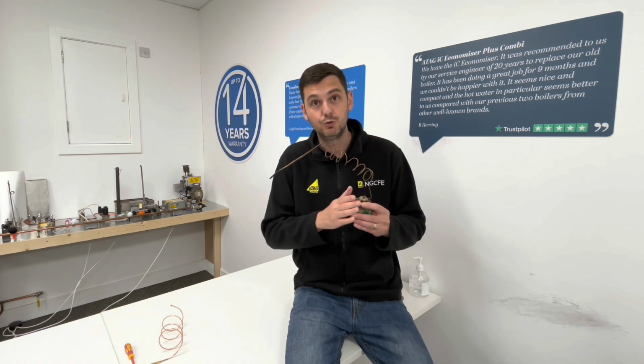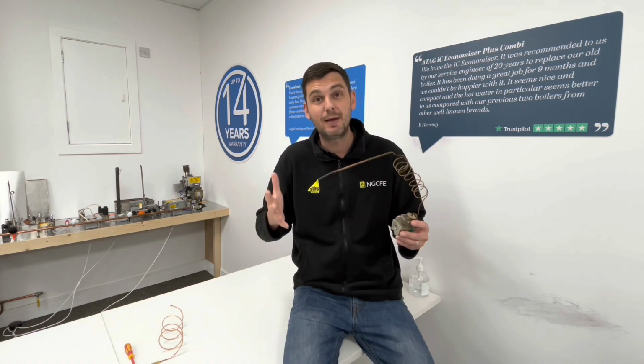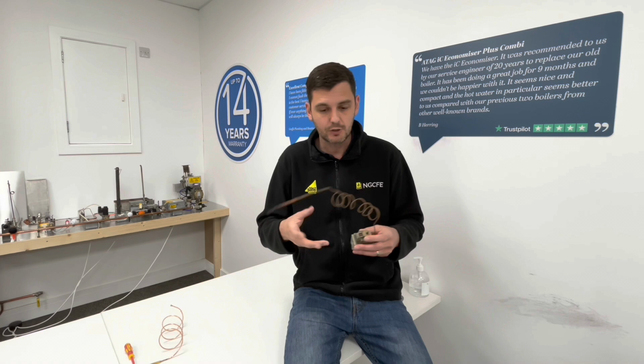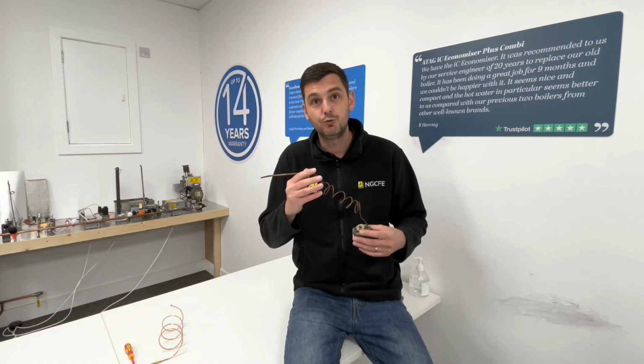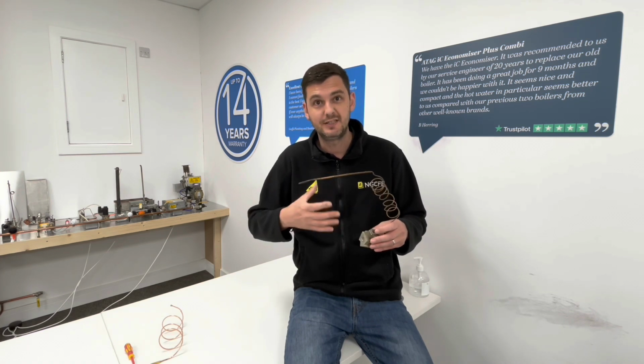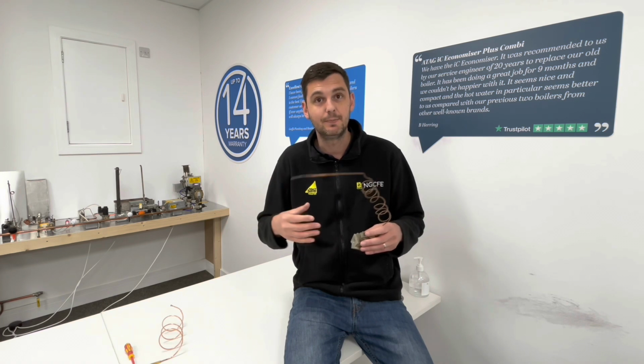And once it's heated, there's a vapor inside it, and the vapor will expand and travel down this tube, the capillary tube, and it will always either open or close something. It's usually a set of bellows. However, in the case of an electric thermostat, it can be a micro switch. So it always opens and closes something. However, in most cases, it's either bellows, or in some cases, it can be a micro switch.